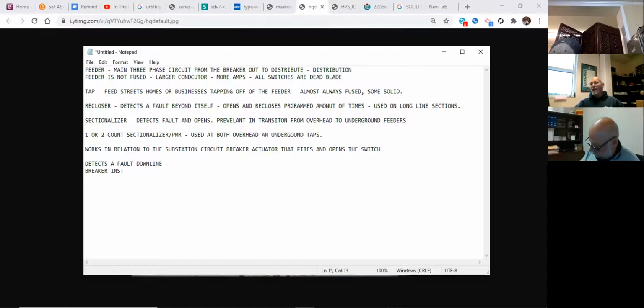When an instantaneous happens, who's answered that? Tim, when we have an instantaneous on a breaker, what does the breaker actually do mechanically? Does the breaker open and close? It does, yes. This is the reason why we have count in here, and we're going to use a 2-count sectionalizer for this example. The sectionalizer counts one loss of voltage.